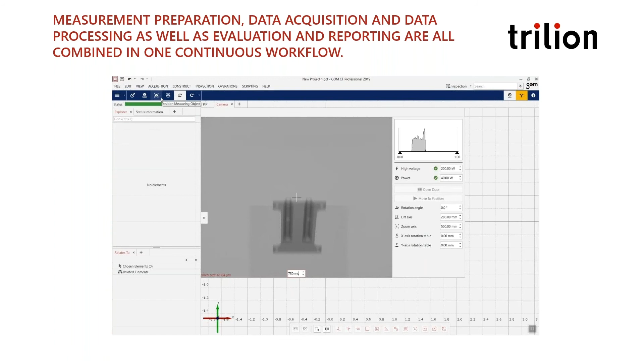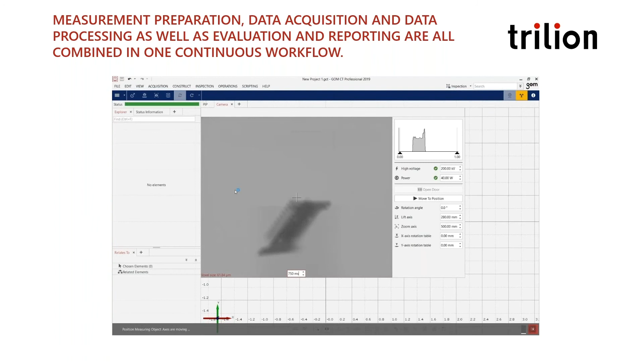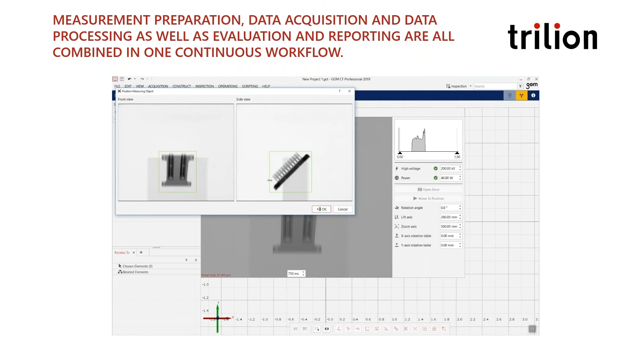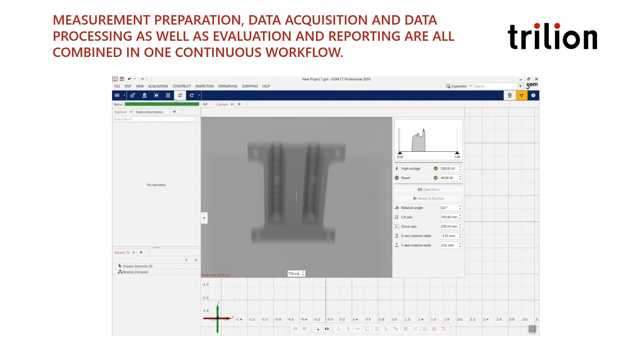You'll see here a live view of whatever you're scanning. This is a small electrical connector. What you're going to see here first, we've already powered up the machine. What it's doing now is the auto centering operation. This is pretty much one of the only parts you have to interact with manually. You have to draw this green box around your part wherever it may be in your measuring area. Once you hit OK, it automatically pulls your part to the center of the detector, which allows for a higher resolution from being in the perfect center of the detector. And like I mentioned earlier, it's a much faster workflow as far as industrial CT goes.